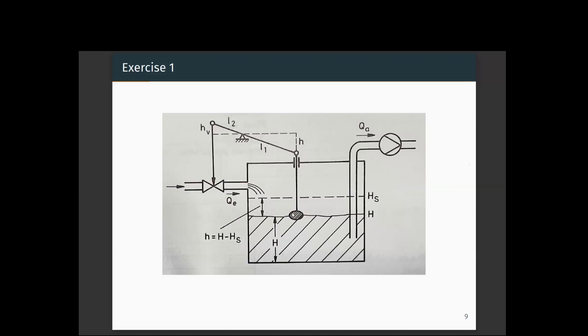The sensor here is the float. This float moves up and down according to the level of the water, so the water level is sensed by the float. Based on the position of the float, if the water level is higher, the float position will be higher, and it will correspondingly give instruction to the inlet valve. We will have a certain desired set point — HS denotes this set point — and our aim is to maintain the level of the water at this set point.